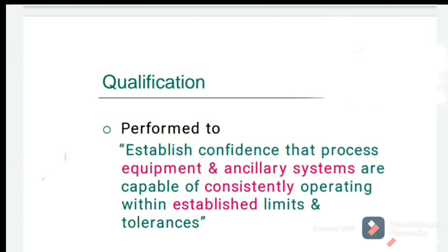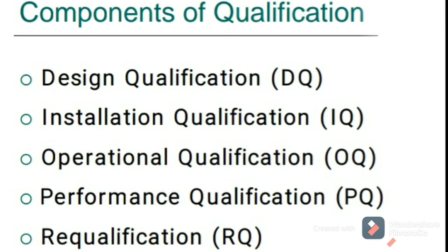In installation qualification we see what documents are required for the instrument. When and where we receive it, condition upon receipt, complete order receipt, transport to the site of use, and unpacking. These are all documents required when we unpack the instrument. After unpacking, the next process is installation: by whom, where is the location, and on what date we install the instrument. Next is checkup and self startup, to see whether it is working or not. We then do the equipment calibration and cleaning.